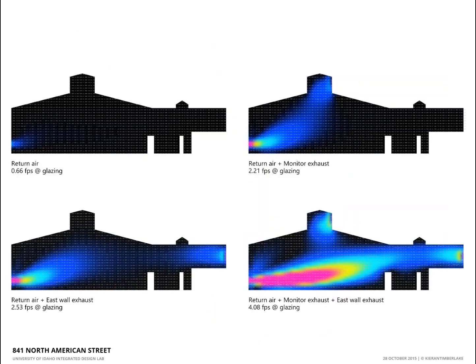So we combined these types of assessments with modeling, as is normally the case, and began to look at some of the CFD models that we had run in these spaces and found that some of the distribution that we were actually measuring with our sensors and what we were modeling showed that we were seeing a pattern of air movement that perhaps was not quite as thorough within the space as we would have liked. Ideally, we would have seen something like this, where we would have seen some purging throughout a larger portion of the space. And we actually used the sensor data in conjunction with this modeling software that we cooked up to determine whether or not there'd be value in installing east side fans.